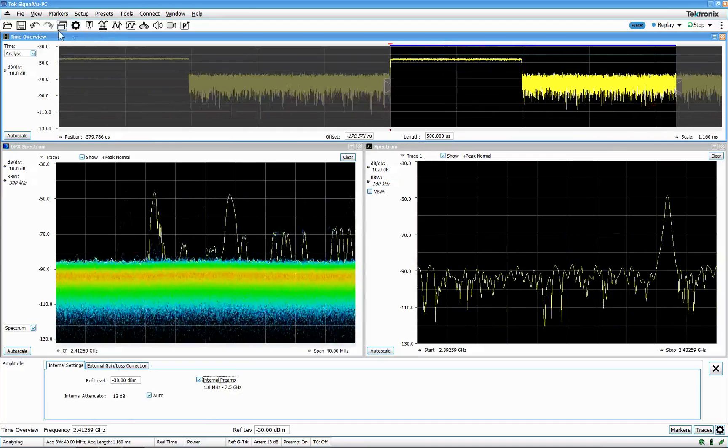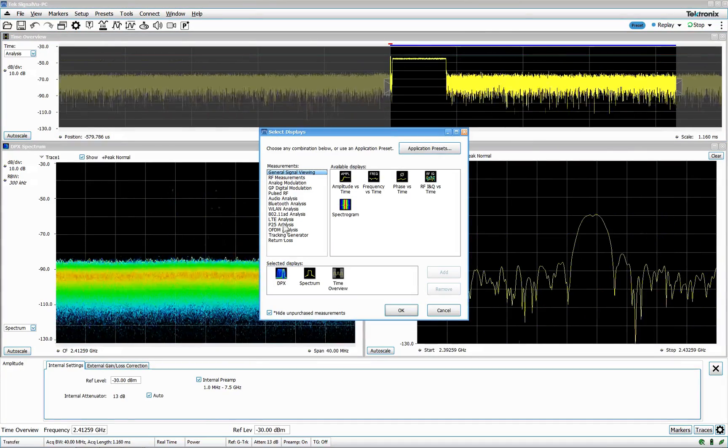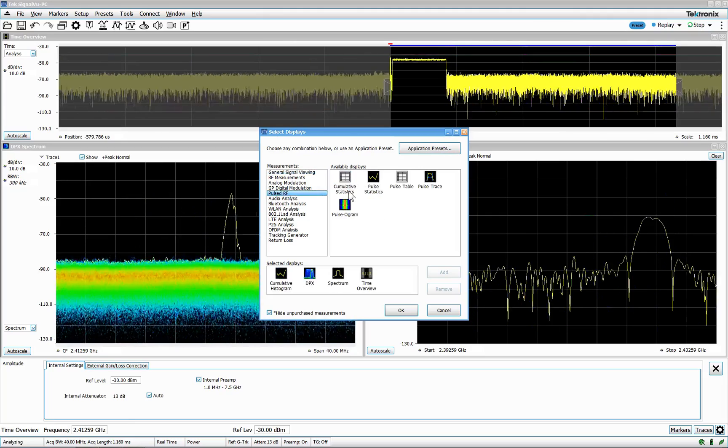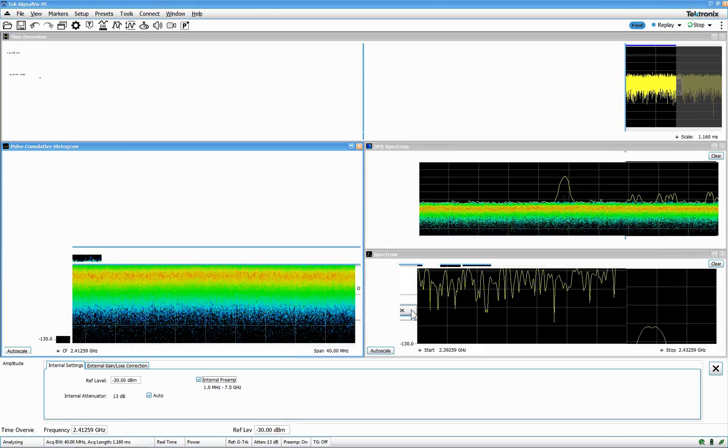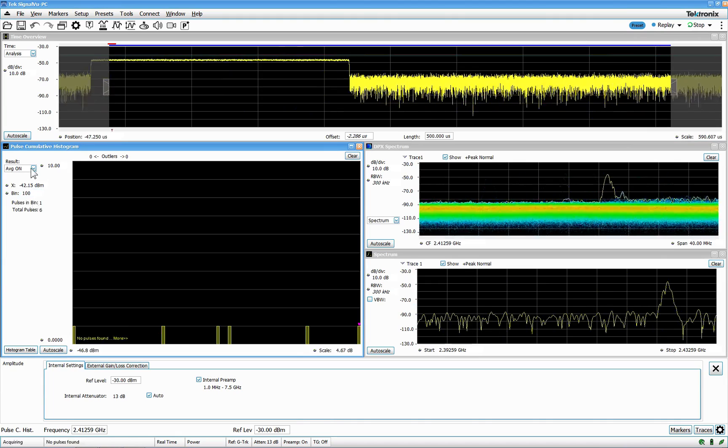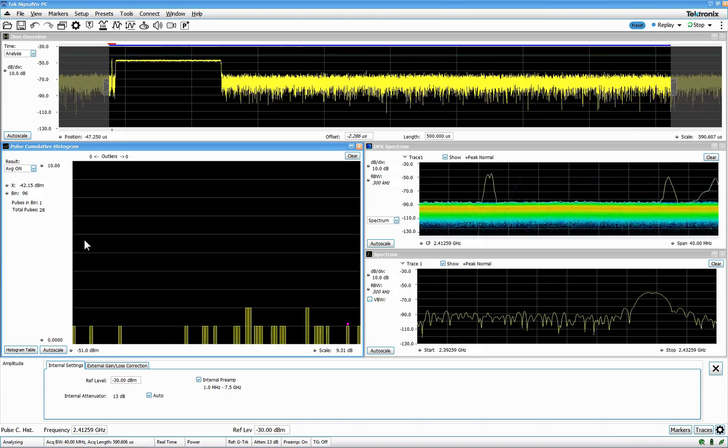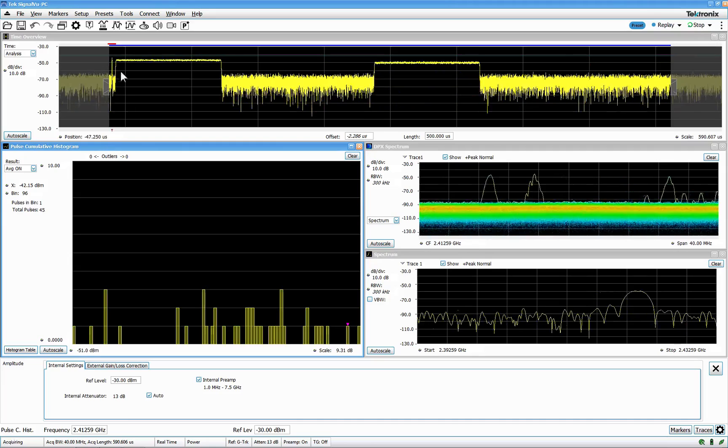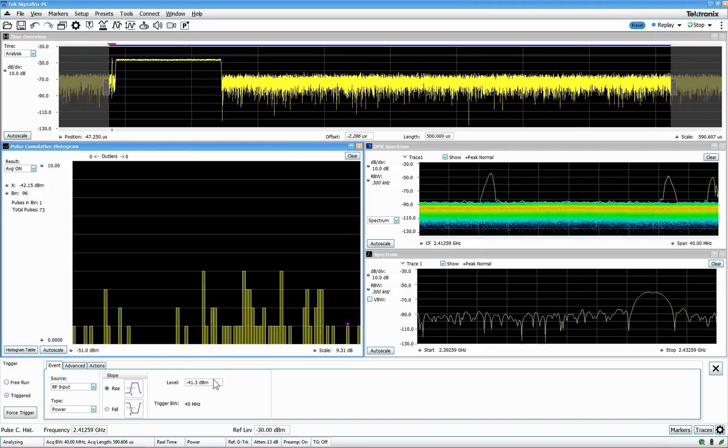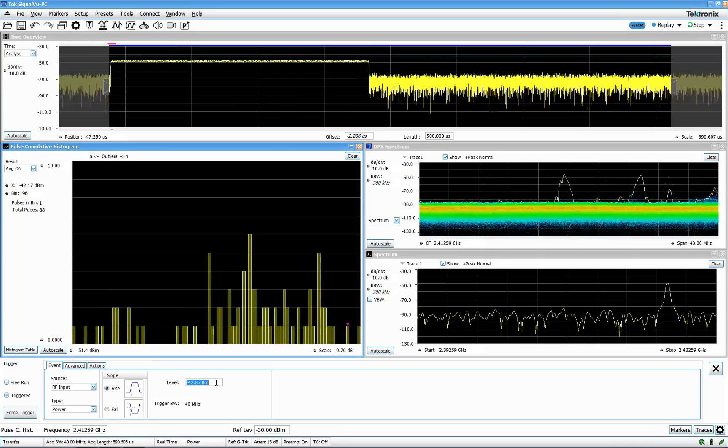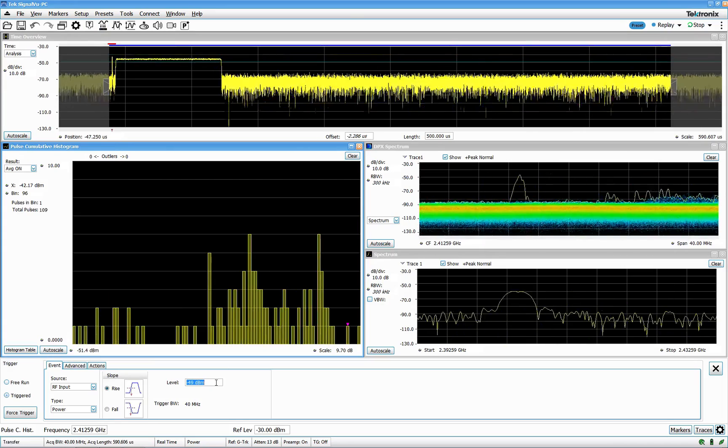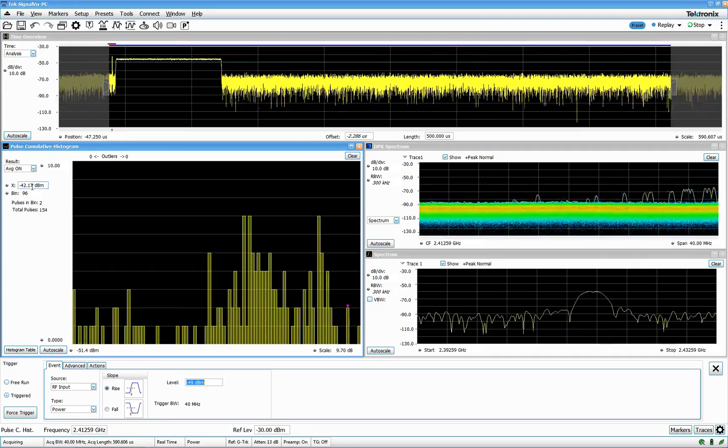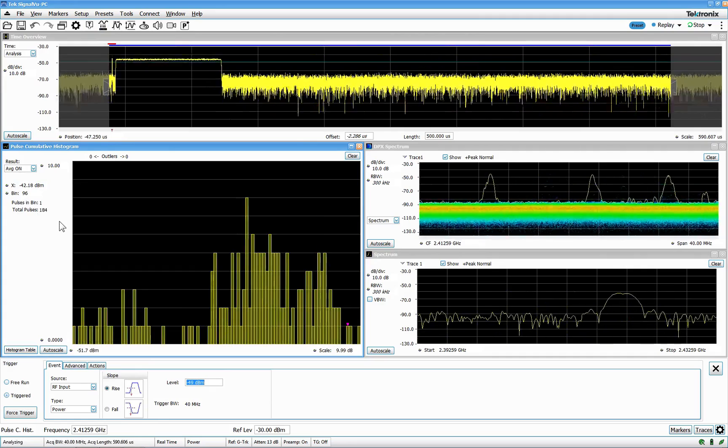Next thing I will do is go in here and go for the pulsed RF and just look at it. So we have a histogram here and we look at the average on power. You can see it's just accumulating. So we have 30 pulses right now. To tweak the trigger a little bit, like this. This is better and you can see how many pulses we have.